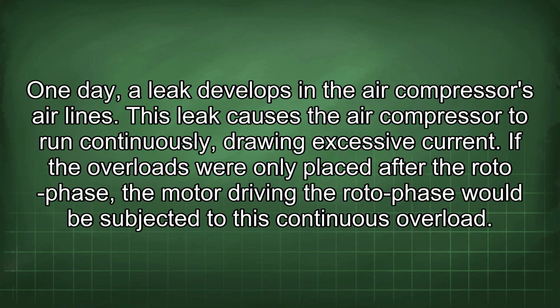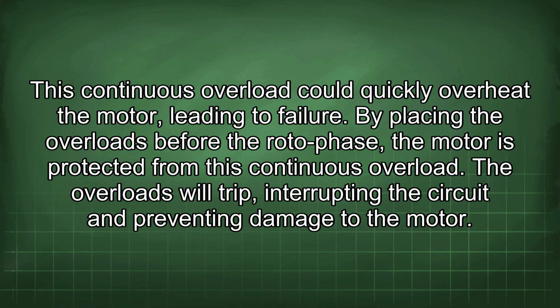One day, a leak develops in the air compressor's air lines. This leak causes the air compressor to run continuously, drawing excessive current. If the overloads were only placed after the roto-phase, the motor driving the roto-phase would be subjected to this continuous overload. This continuous overload could quickly overheat the motor, leading to failure. By placing the overloads before the roto-phase, the motor is protected from this continuous overload. The overloads will trip, interrupting the circuit and preventing damage to the motor.